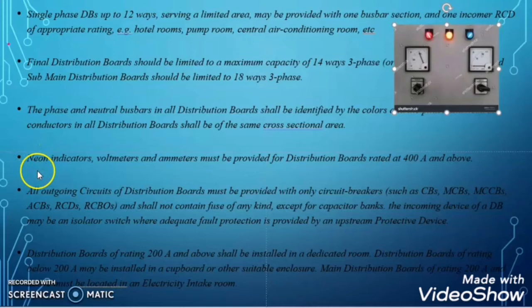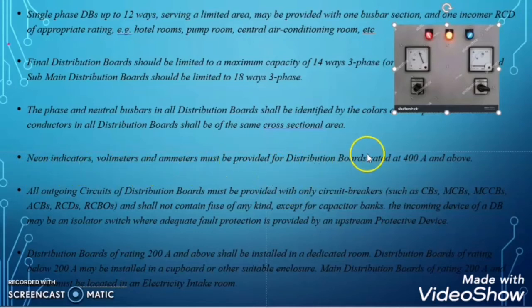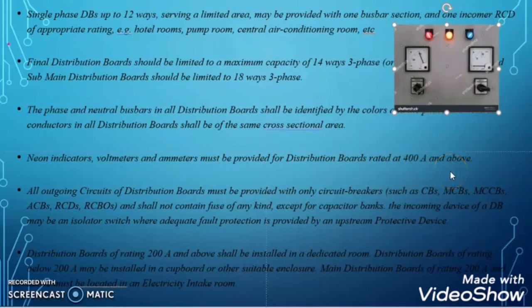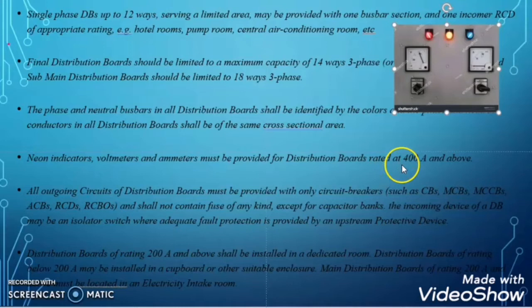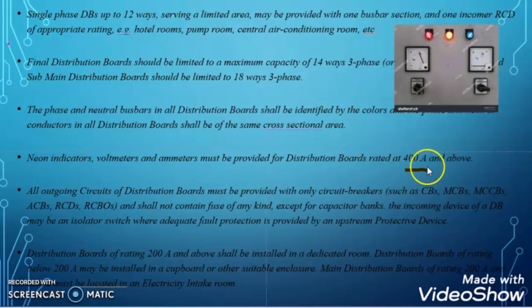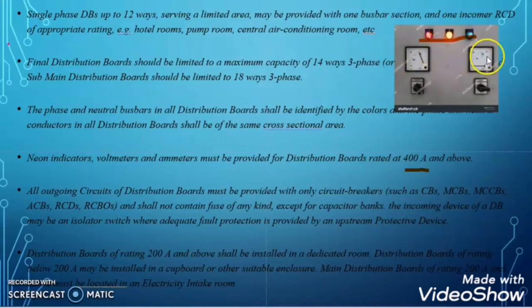The neon indicator, voltmeter, and ammeter must be provided for any distribution board — whether FDB, SMDB, or MDB — if the incoming rating is 400 amperes or above. These instruments are required to monitor phase availability and electrical parameters for higher-rated distribution boards.